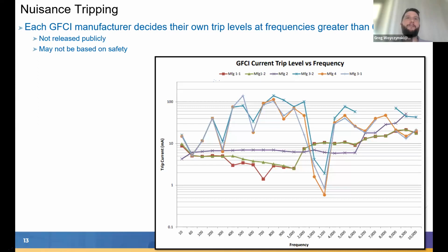So each GFCI manufacturer decides their own trip levels at frequencies greater than 60 hertz. We just talked about that. And this graph proves that. This is test data. Each different color line is a different model of GFCI. And there's a few things we notice about this graph. This graph shows trip current versus frequency. So for example, this gray star here means this model, manufacturer 3 model 1, at around 500 hertz is tripping at about 100 milliamps. When that donut senses about 100 milliamps, it's tripping at 500 hertz.